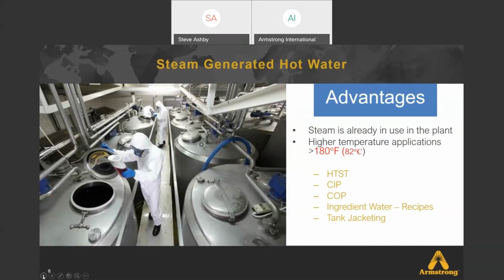So certainly some advantages of generating hot water with steam is that that's what we know. That is what most plants have used for years. It's available, and it certainly can address higher temperatures of greater than 180 and address a variety of your process needs as far as high temperature short time, clean in place, clean out of place, ingredient water for recipes, and then tank jacketing. These are some pretty common process applications in food and beverage plants, and steam is available and can address not only the lower temperature applications, but certainly the higher temperatures as well.